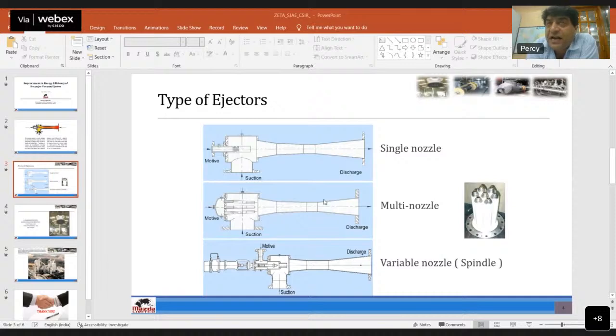Whenever clients or plant people order equipment, they order equipment at 100% capacity, but it happens that at lower capacities the plant operates many a time. And if you do not have such type of installations, you unnecessarily keep on consuming a higher amount of steam, though the plant is not running at 100% capacity. So these ejectors are developed by us specially for the Indian market, where the plant operates at lower than 100% capacity, and you have almost a linear saving in steam, which is again, as I said, very costly.